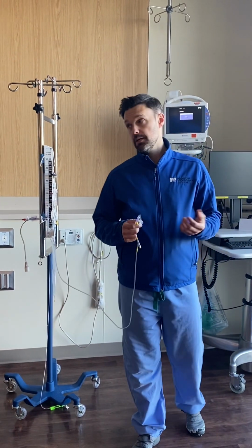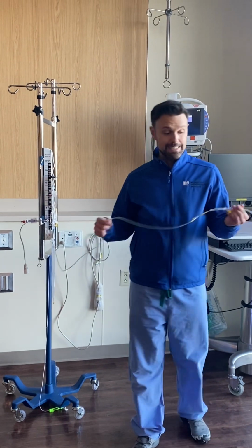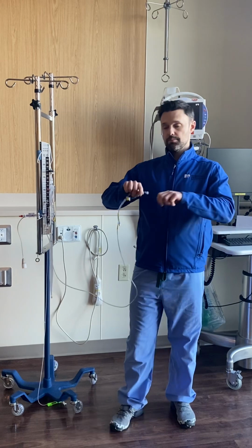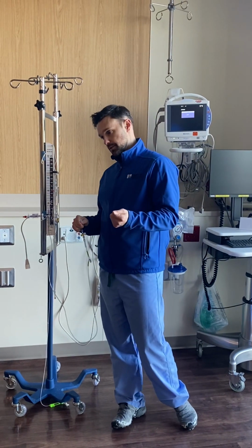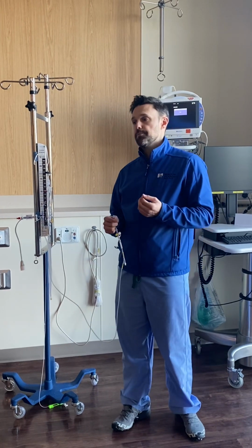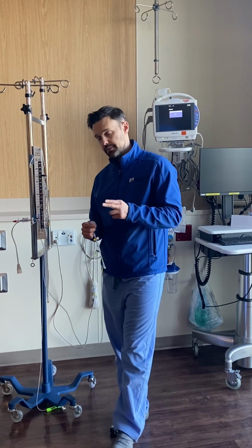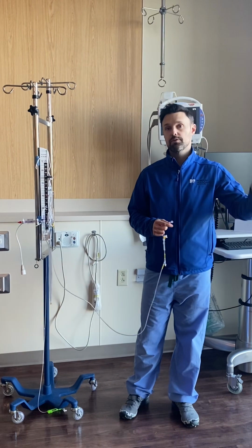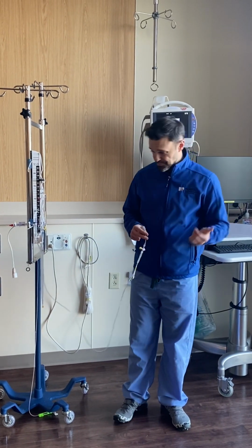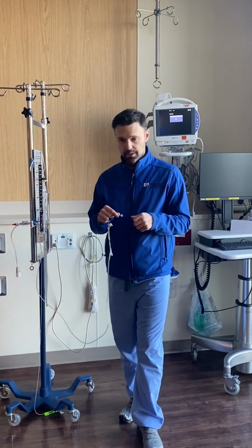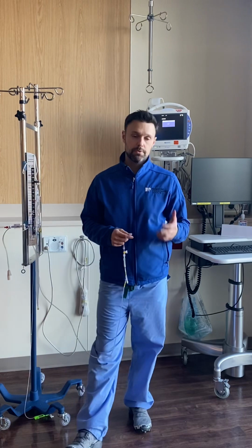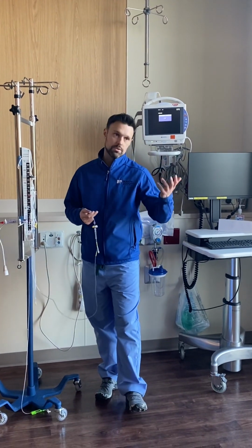Sometimes they can become disconnected, so that happens, right? So what happens if this piece comes disconnected from your catheter? You want to grab a Kelly or some sort of clamp, whatever you guys call that, and you want to clamp off your EVD catheter because you don't want that fluid just running out, right? So you clamp off the EVD catheter. Common mistake is that you want to put this back together. Don't do that. There's a risk for infection. Okay, so just clamp it, call us, let us know what's going on.